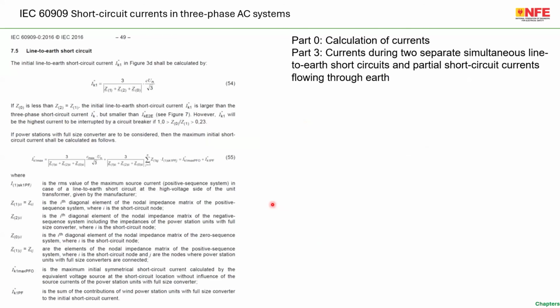The short circuit calculation, line to earth: the term short circuit is used, not fault. Short circuit in the sense that a line is in touch with a metallic part, so the impedance of the fault is considered 0. So it is termed a short circuit.